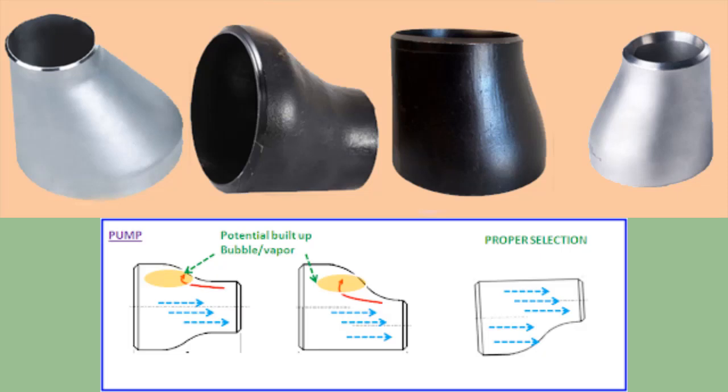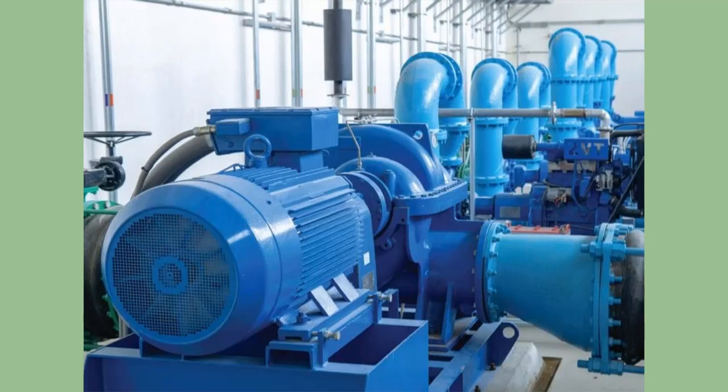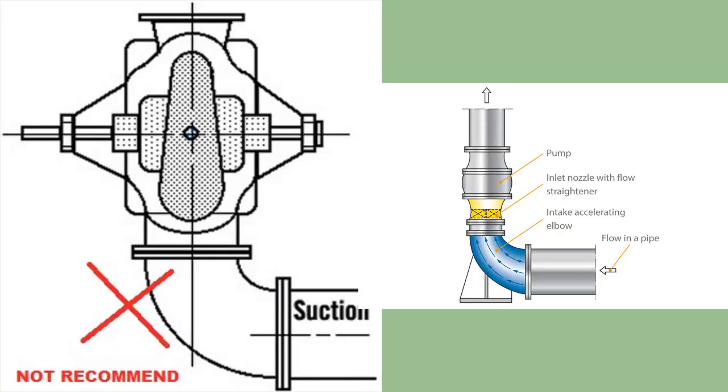Number three, use eccentric reducers on the suction side. Consider using eccentric reducers on the suction side of the pump when a pipe size transition is required. Install the flat side of the reducer on the top when fluid is coming from below the pump.